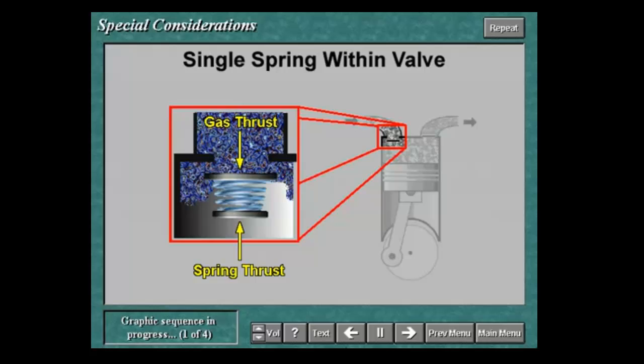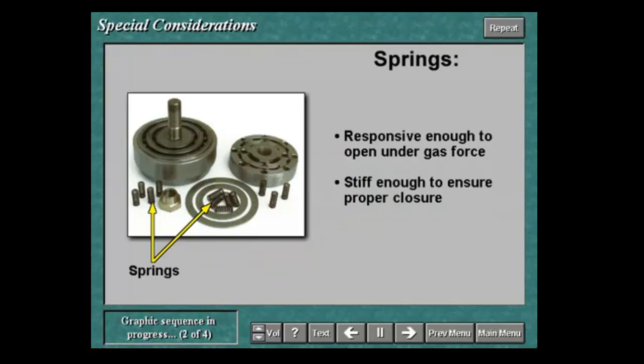Springs must be selected so that they are responsive enough to allow the rings to open under the gas force and to avoid vibration. They must also be selected so that they are stiff enough to ensure closure after the dead end of the stroke.